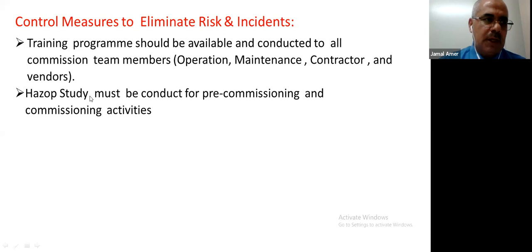for the project. As you know, before starting any new facility or any upgrade of a facility, we have to do a hazard study. This hazard study identifies what the hazards are, and what is required during normal operation. So it's required to define what instrumentation and what protection equipment must be installed in the pipe in case we have high flow, low flow, or high pressure, low pressure. All these variables should be studied in the hazard study, and we select the correct protections against these variables.